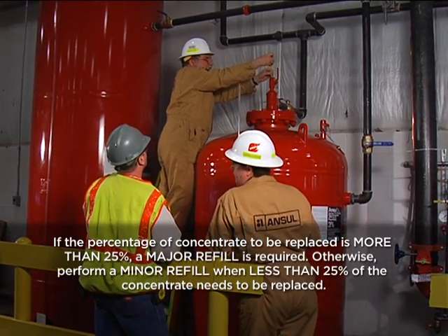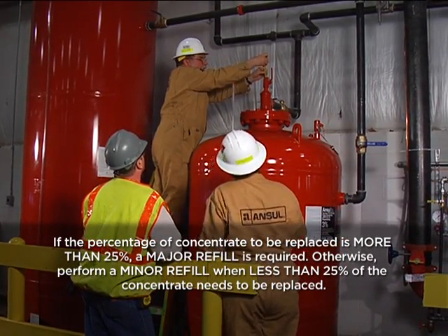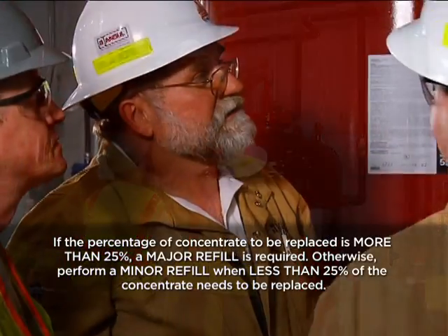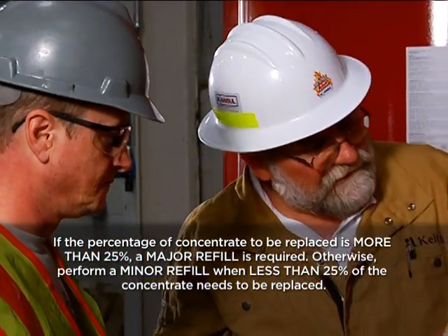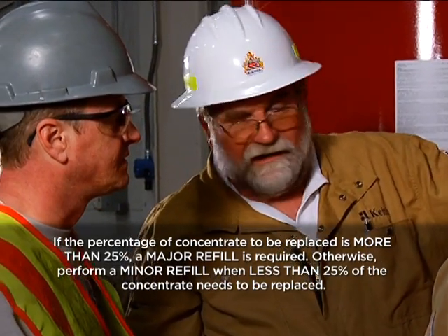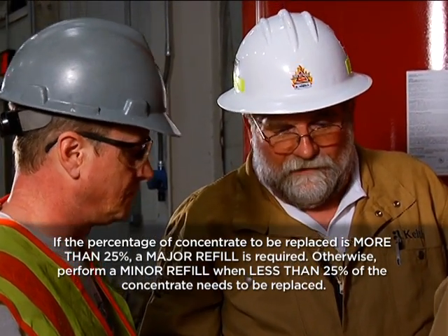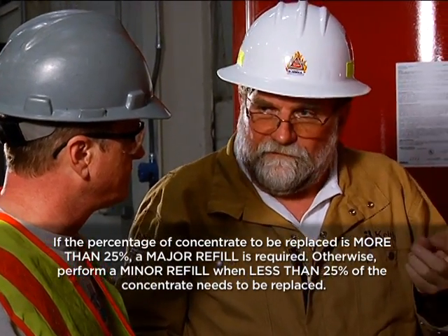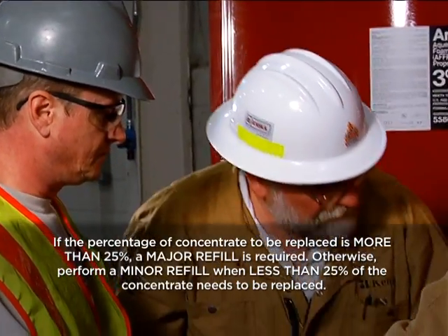If the percentage of concentrate to be replaced is more than 25%, a major refill is required. Otherwise, Ansul recommends following the instructions for a minor refill of the bladder tank when less than 25% of the concentrate needs to be replaced.